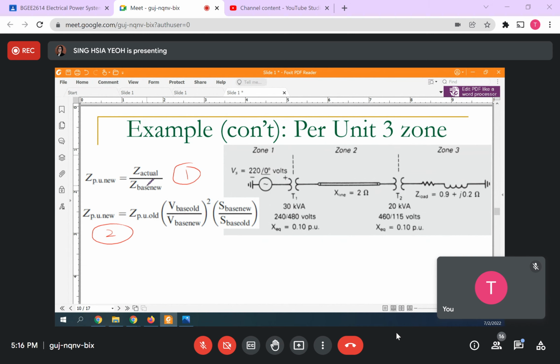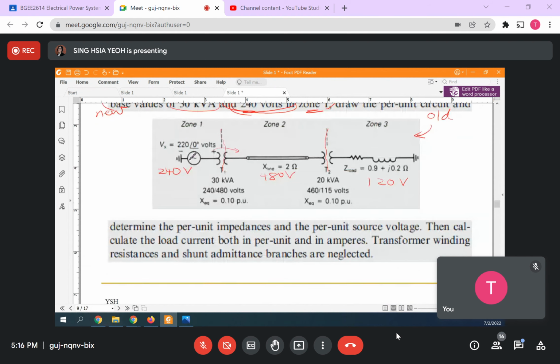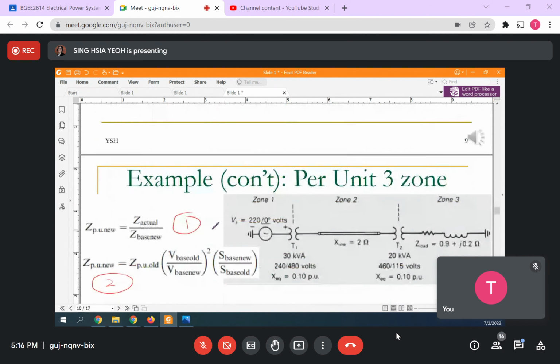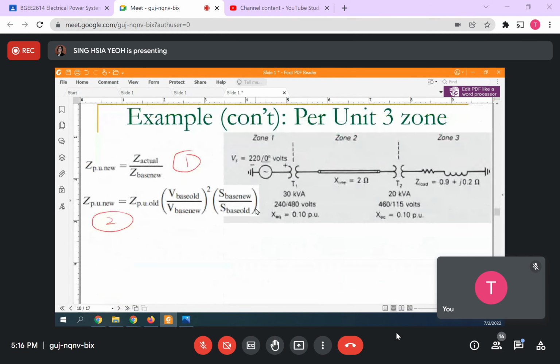220 is the actual, base value is 240. Zone 1 here, 240, actual is 220. So then we write VS PU equals to 220 divided by 240. So you get 0 point something.